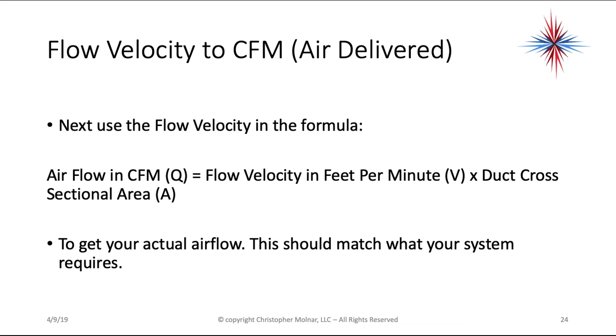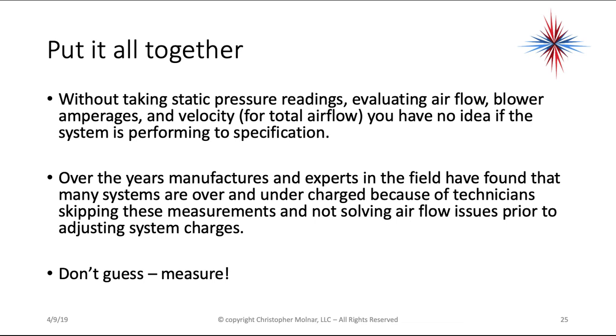If the airflow doesn't match what your system requires, you have a problem that's not refrigeration related. To put it all together: without taking static pressure readings, evaluating airflow, blower amperages, and velocity, you have no idea if the system is performing to specification. Over the years, manufacturers and experts have found that many systems are over- and under-charged because technicians skip these measurements and don't solve airflow issues prior to adjusting system charge. The bottom line is: don't guess — measure.